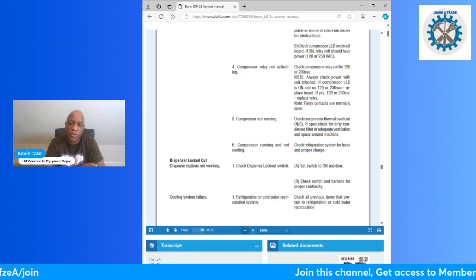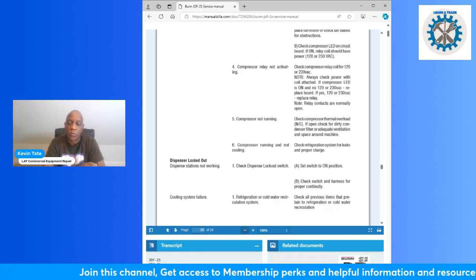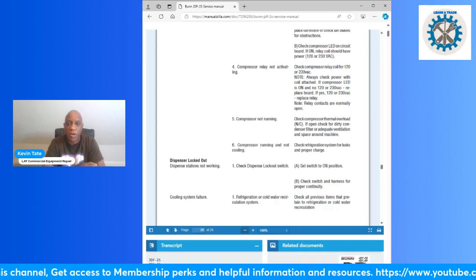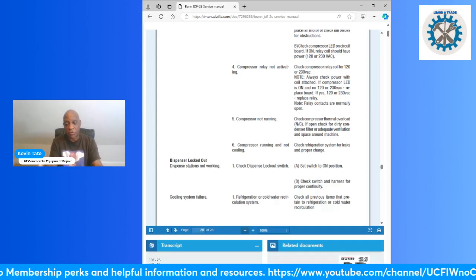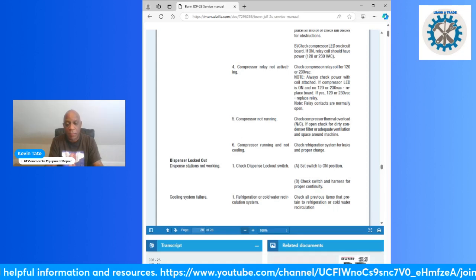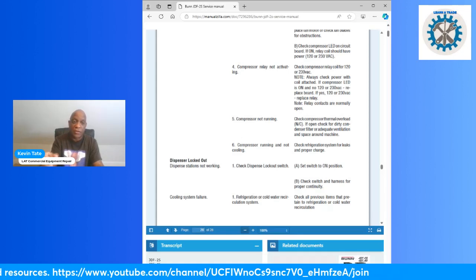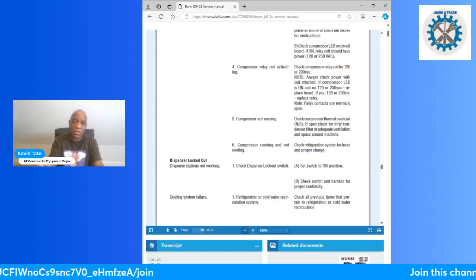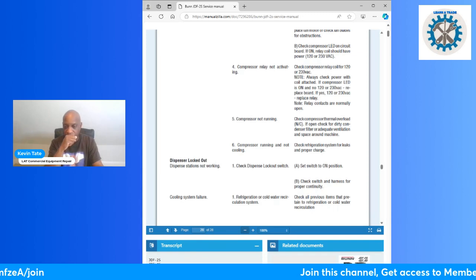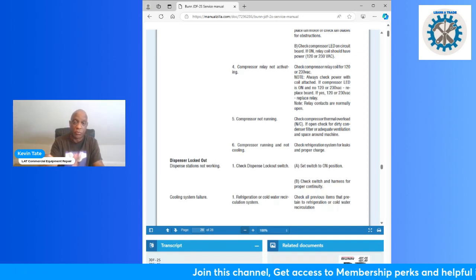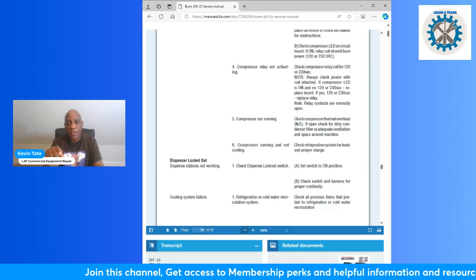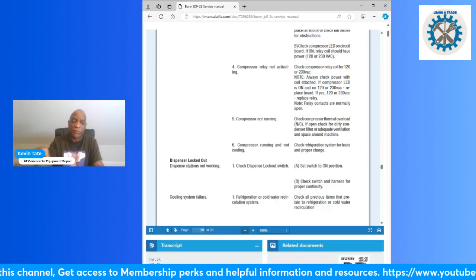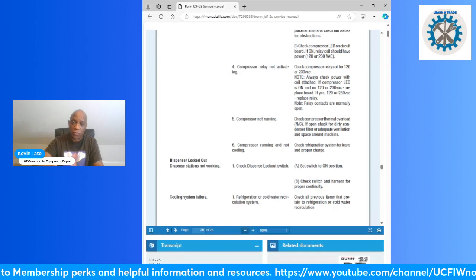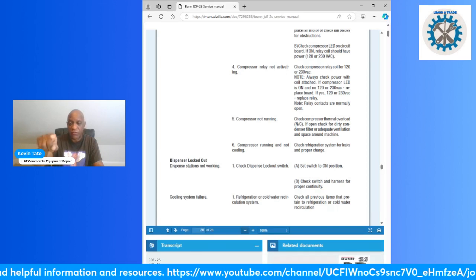due to when you first install these JDF-2s, you have to make sure your water level is at the proper level. And as I said before, you take that lower panel off. When you take that lower panel off, on your right, you're going to see clear tubes. You're going to see a drain tube, and then you're going to see a fill tube. You're going to see a tank tube. I'm sorry. So that tank tube, it shows the level of the water inside that tube. You can watch it. You can actually watch it fill.